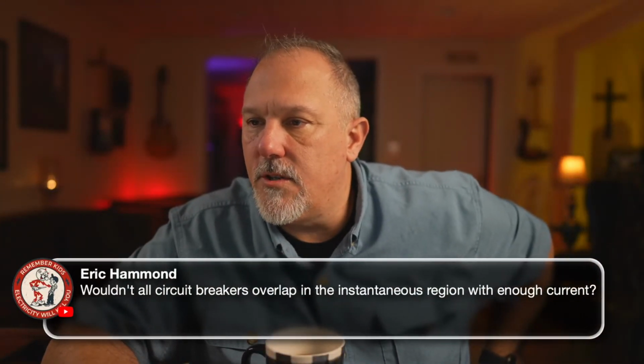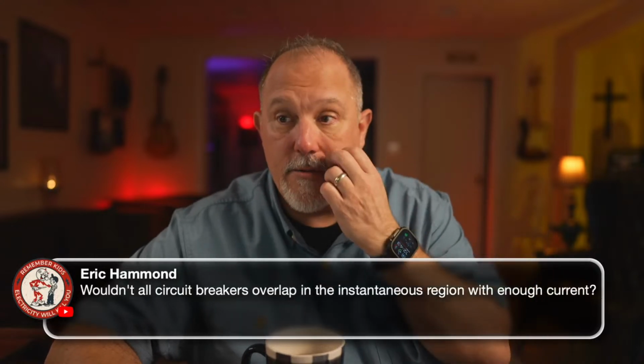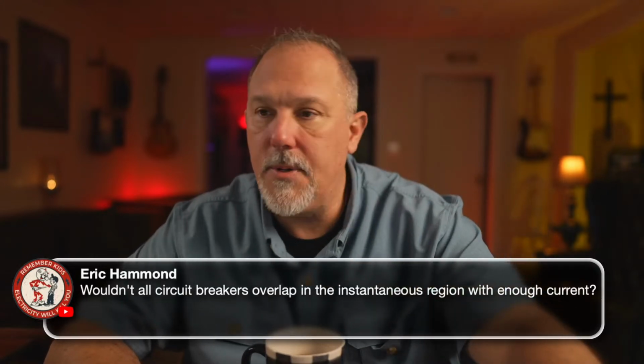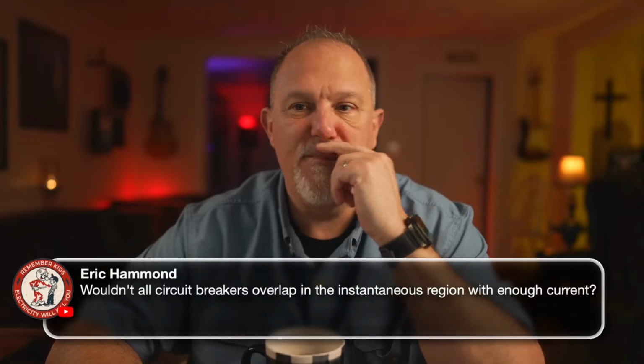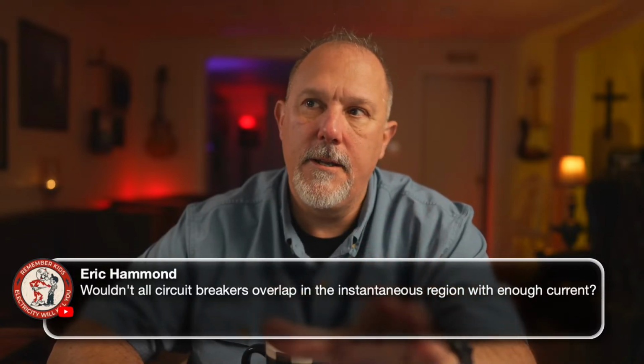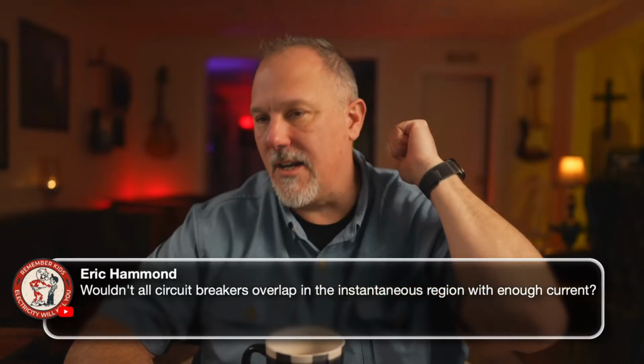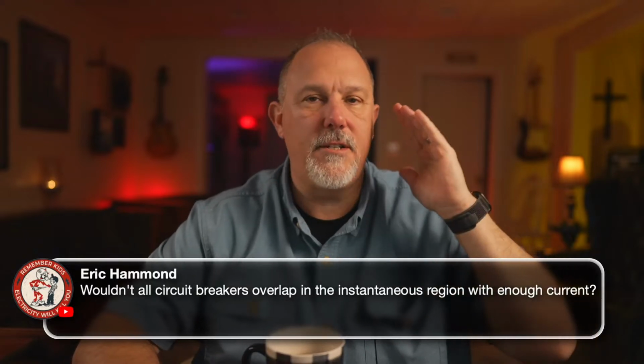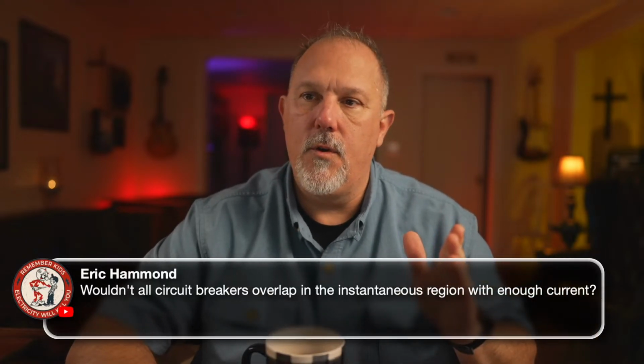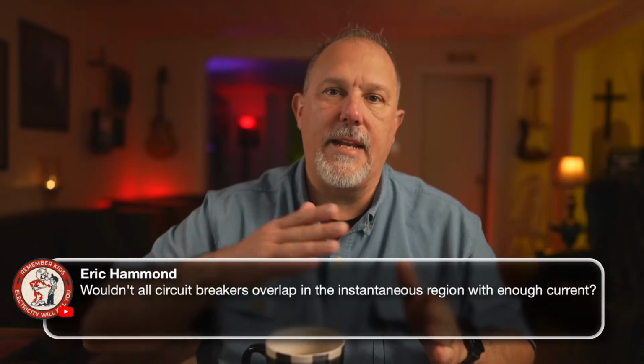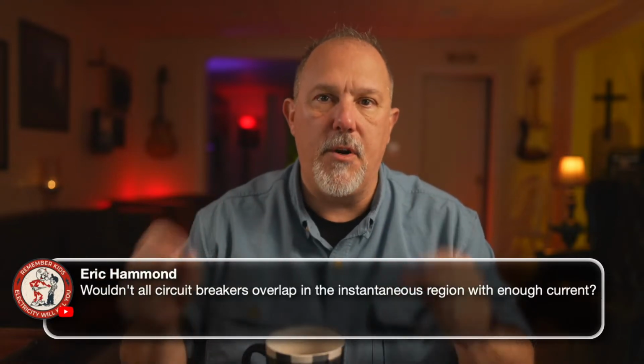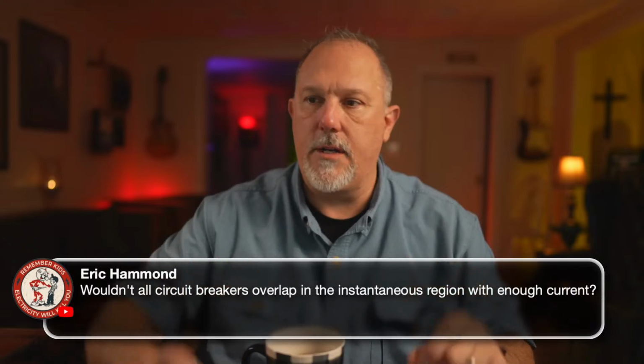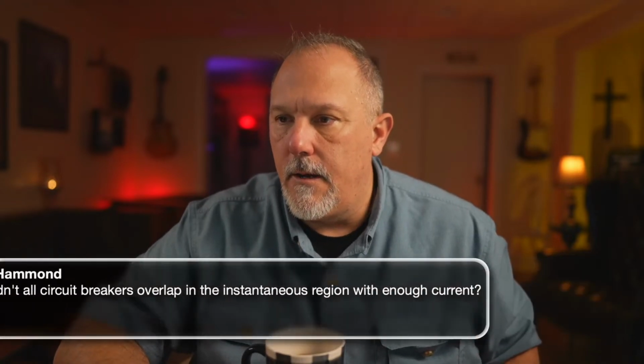Okay, so that was our last one. So my only advice, Eric, is, and I do this too, I talk about overlapping in the instantaneous region, but really it is any fault current that exceeds the instantaneous pickup of both overcurrent devices, both breakers. All right.